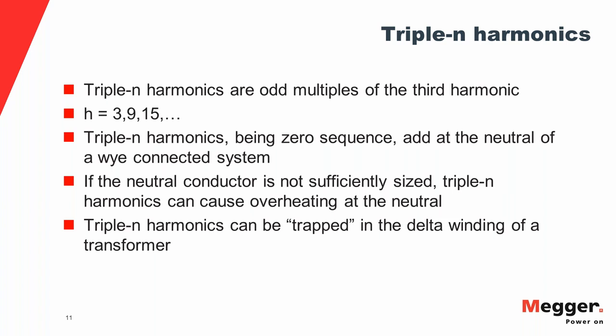Triple N harmonics are odd multiples of the third harmonic: third, ninth, fifteenth. They are zero sequence harmonics. Because they are zero sequence, the currents flowing through the A, B, and C phases have no phase angle difference between them — they are coherent in phase. When they converge at the neutral, they add up, resulting in the total current flowing through the neutral conductor. If there are large zero sequence harmonics in the system and the neutral is not sufficiently sized, there will be overheating of the neutral conductor.